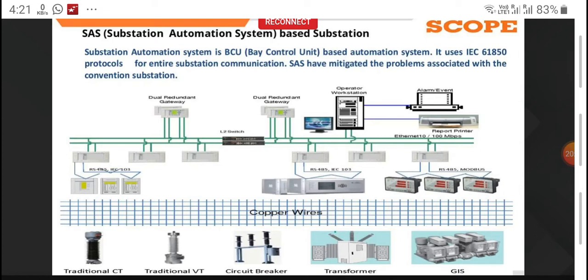But technology evaluation is still going on, and people are concerned about how we can reduce the copper usage from the switchyard to the control room, because we are still using copper cables. So most people have started coming up with a solution called the digital substation. There are many things where we reduce the copper cables, and whatever issues we are facing in the substation automation system, we are addressing those issues in the digital substation system.